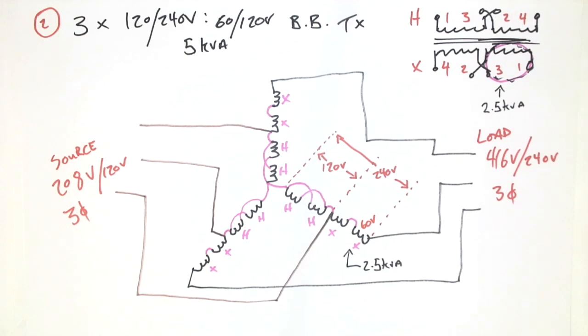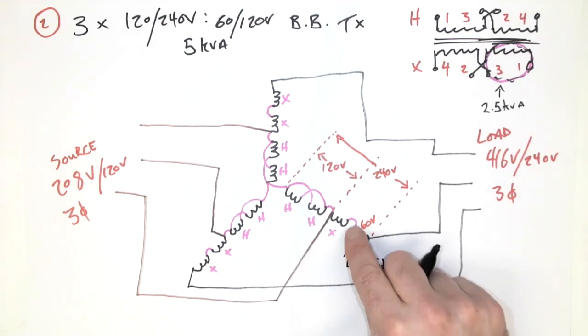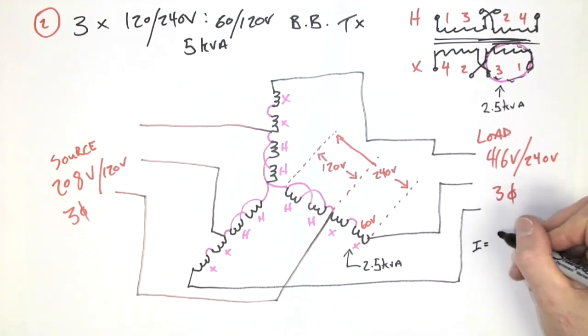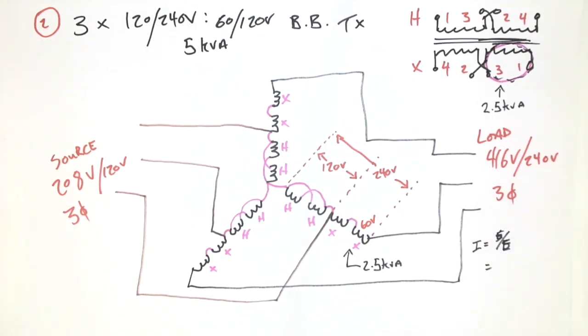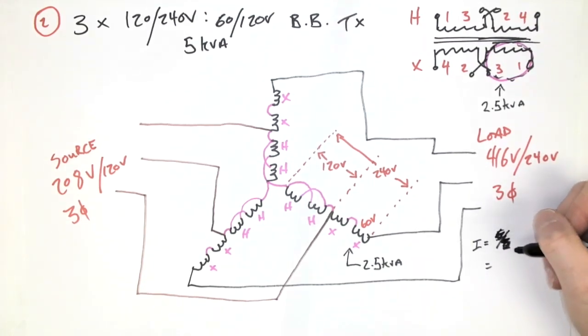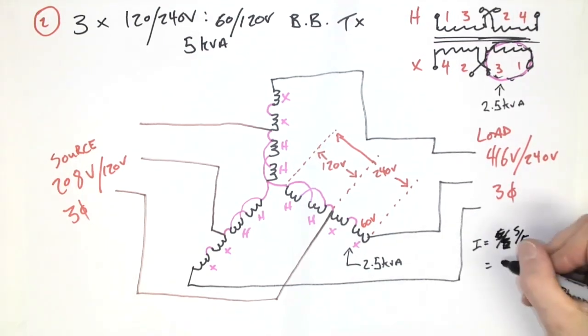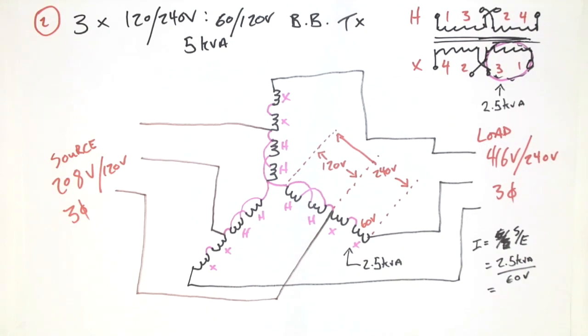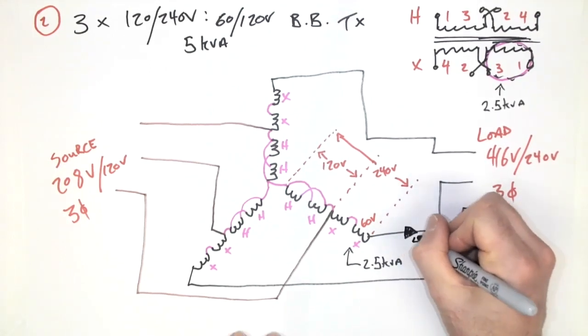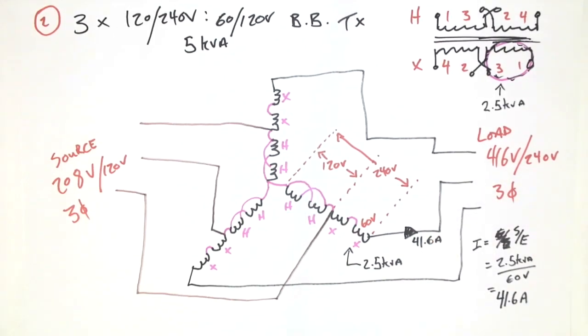So same process as before, we are going to be taking our value of kVA and voltage to work out the rated current. What is the maximum current that 60 volt coil or winding is able to put out? So I is equal to S over E. Sorry about that. So S over E, which is 2.5 kVA divided by 60 volts. And if we do that calculation, it comes out to a fairly high current. There we go, 41.6 amps. All right, so that would be the amount of line current that we could safely provide to our 416 volt three-phase load.